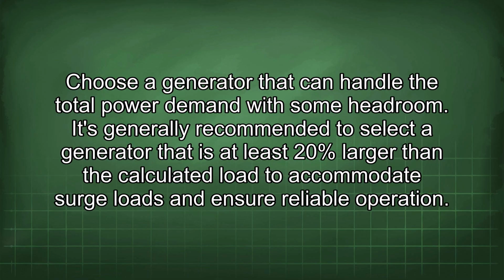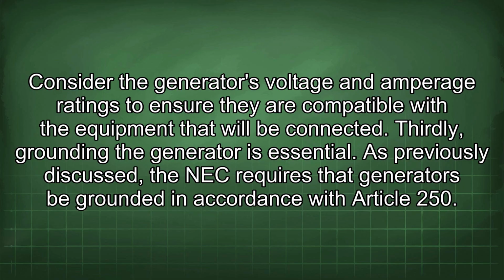Secondly, selecting the right generator is important. Choose a generator that can handle the total power demand with some headroom. It's generally recommended to select a generator that is at least 20% larger than the calculated load to accommodate surge loads and ensure reliable operation. Consider the generator's voltage and amperage ratings to ensure they are compatible with the equipment that will be connected.